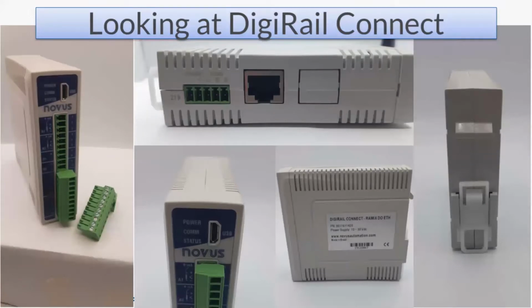This is how DigiRail Connect looks. It is DIN rail mountable and has detachable connectors. Its modern and thin design offers a small form factor for installation in panels. It has LEDs for each input and output individually to show the real state of the I/O for simple visual inspection. The RS-485 and Ethernet interfaces are at the bottom of the enclosure, together with the power supply inputs. It also has three status LEDs: power, COM, and status. Easy to understand their function. The status LEDs start blinking when there is an input error on the I/O module.